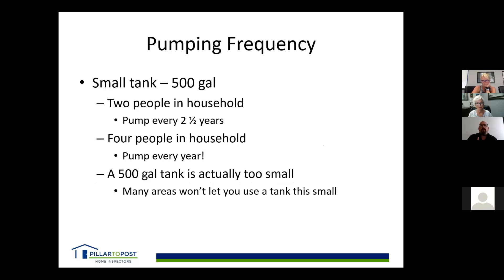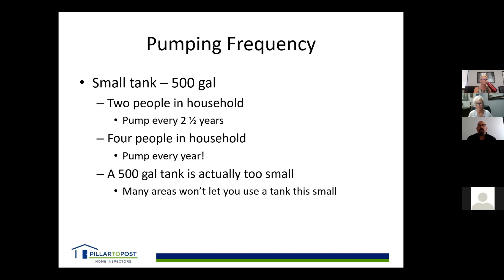A smaller tank of about 500 gallons with two people needs pumping about every two and a half years. With four people and a 500-gallon tank, every one to two years. Realistically, these older 500-gallon tanks are too small, and many areas won't allow you to use a tank that small for a new installation today.